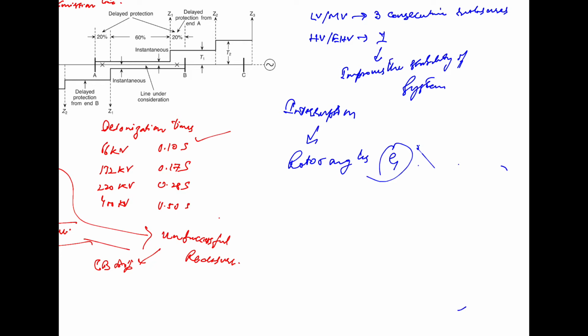Now, since the high voltage and extra high voltage lines are generally the tie lines, there is the presence of a source at both the ends. So in order for the transient fault arc to be quickly quenched, the line must be instantaneously and simultaneously tripped from both the ends before a reclosure can be attempted. So this must be taken into consideration.